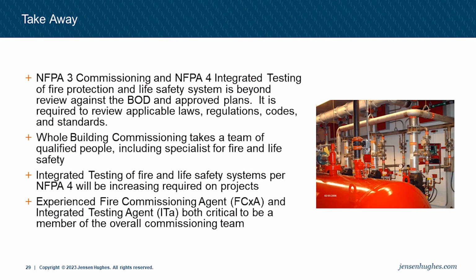So what are some of the takeaways? NFPA 3 commissioning and NFPA 4 integrated testing of fire protection and life safety systems go way beyond review of the basis of design in the OPR. It's required to review applicable laws, regulations, codes, and standards—because part of this is trying to make these buildings safe for occupants.